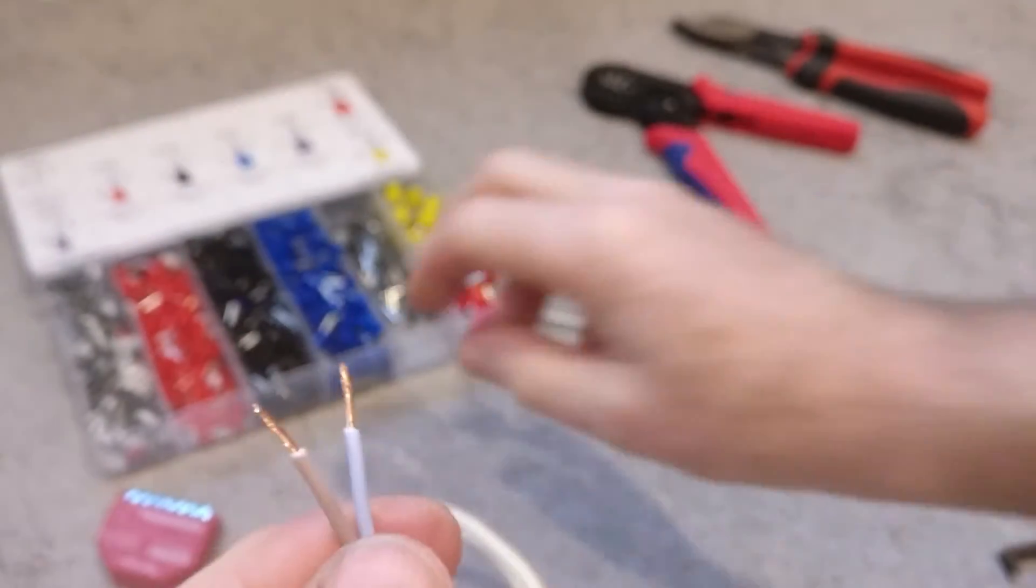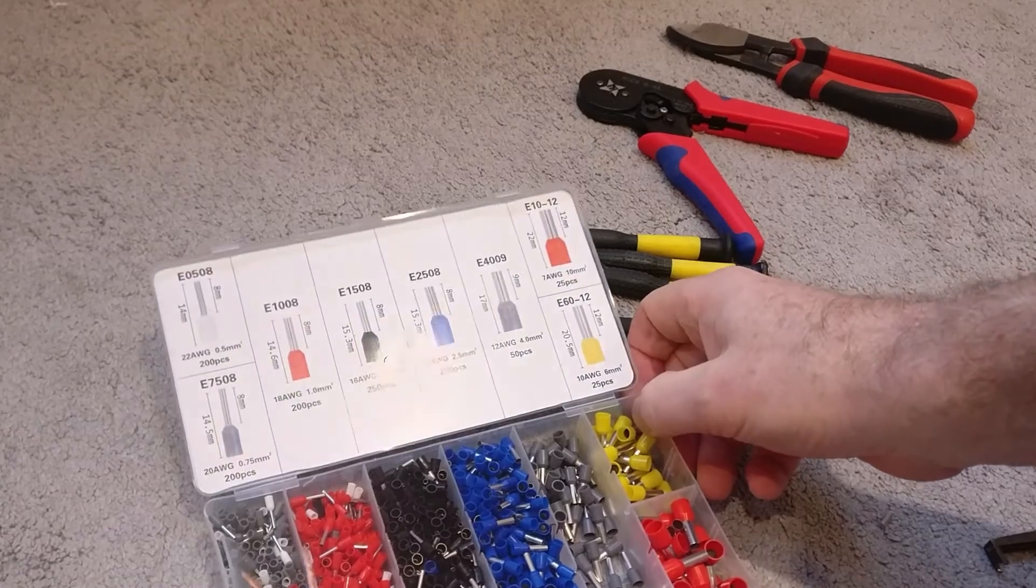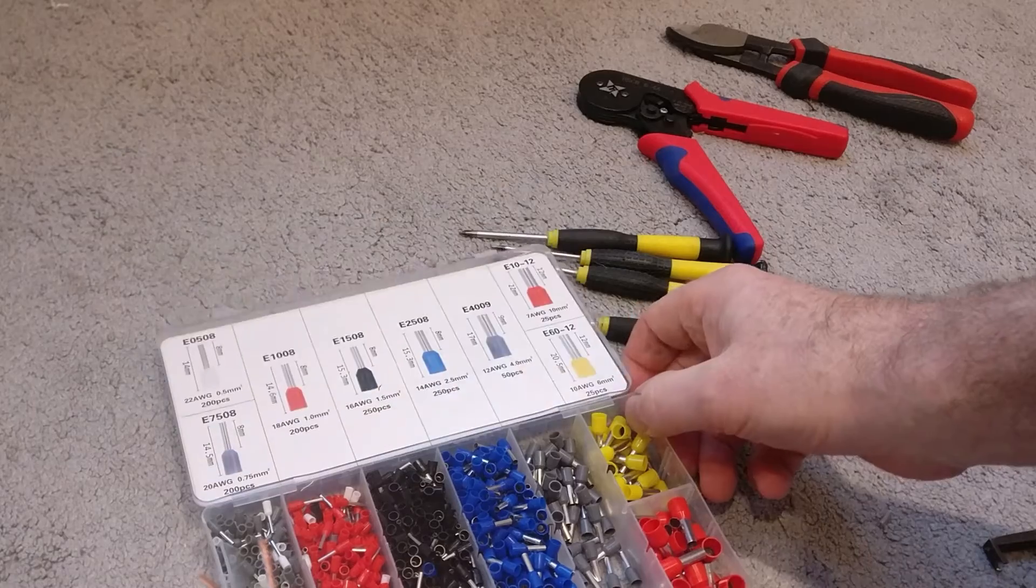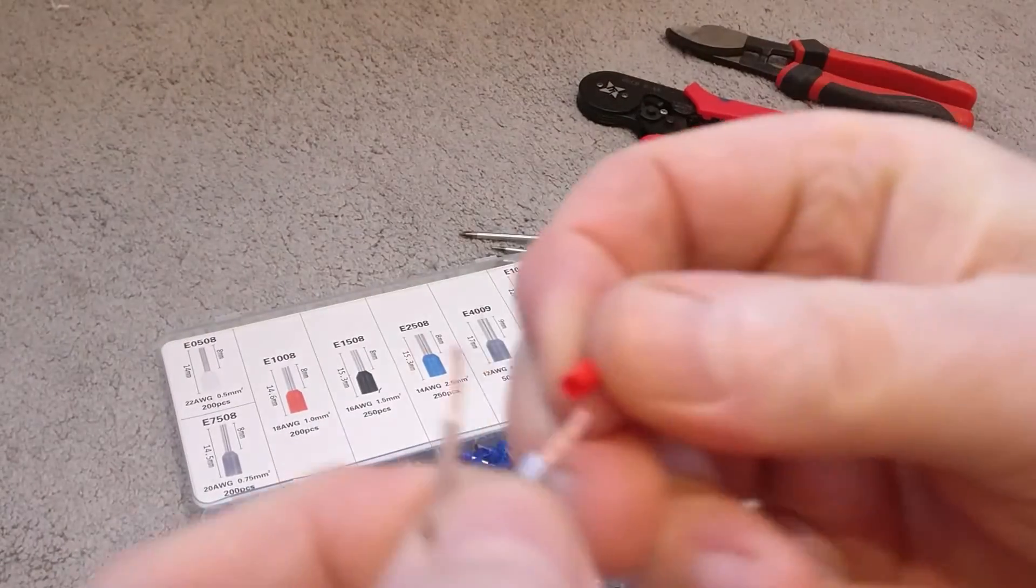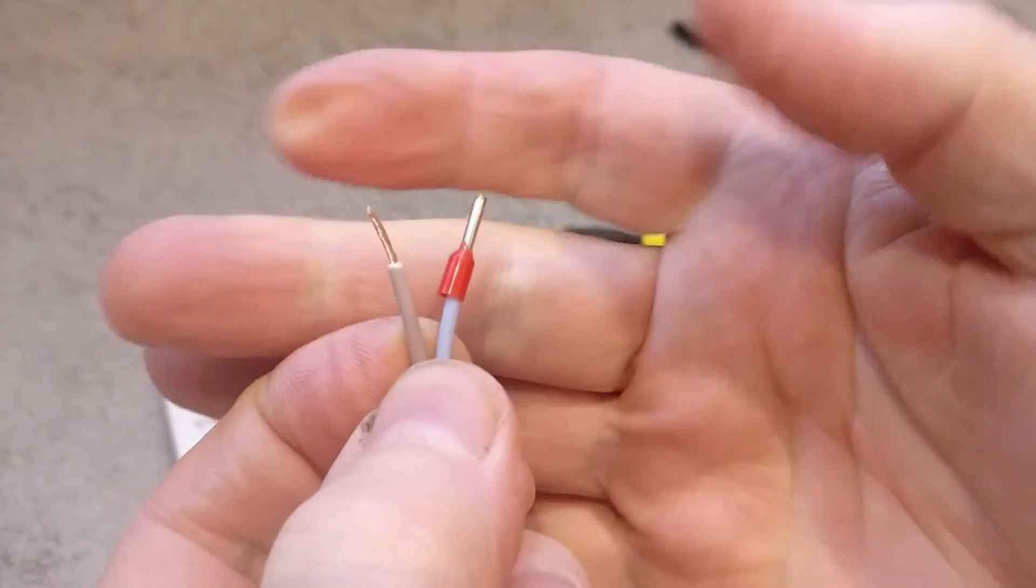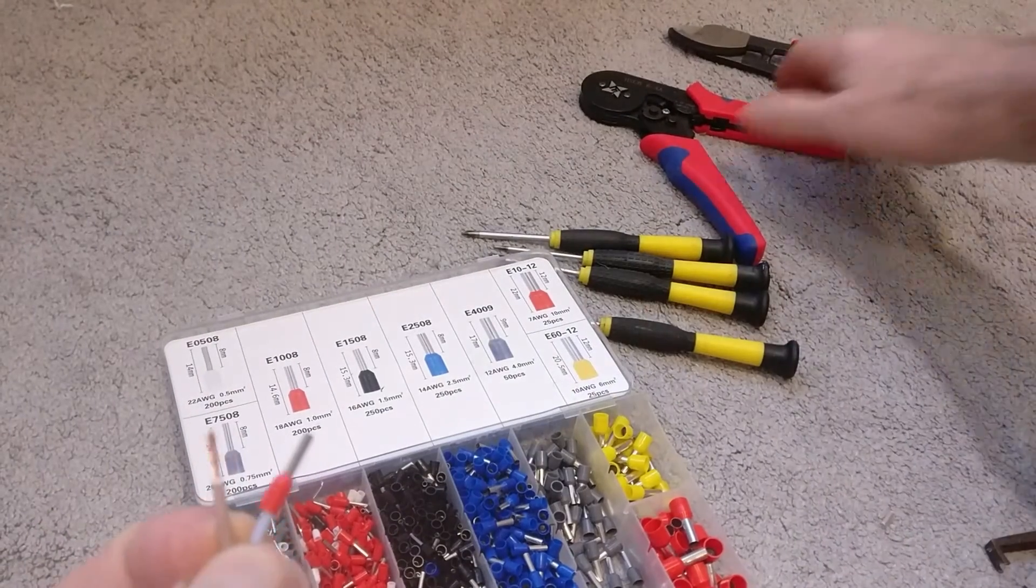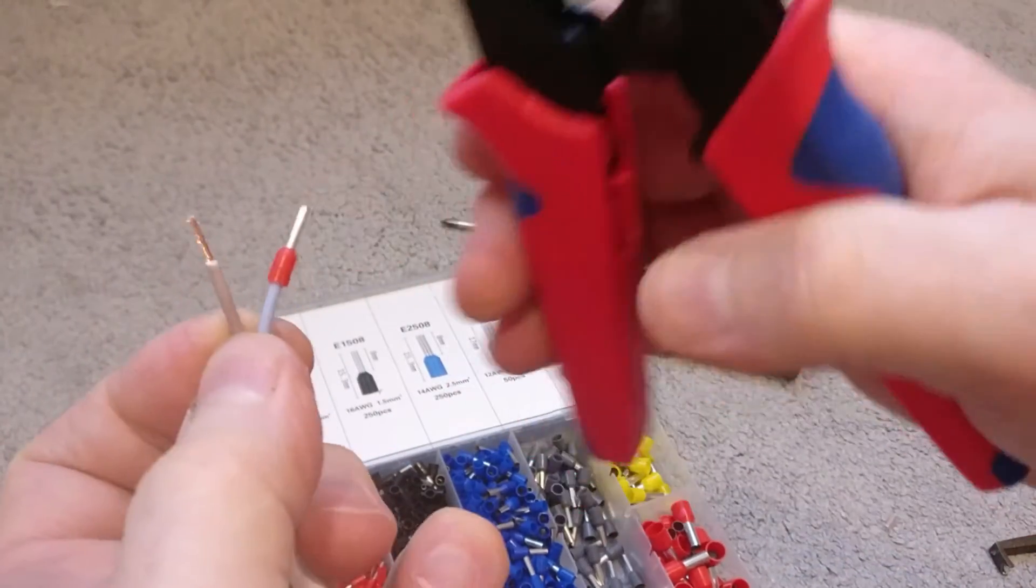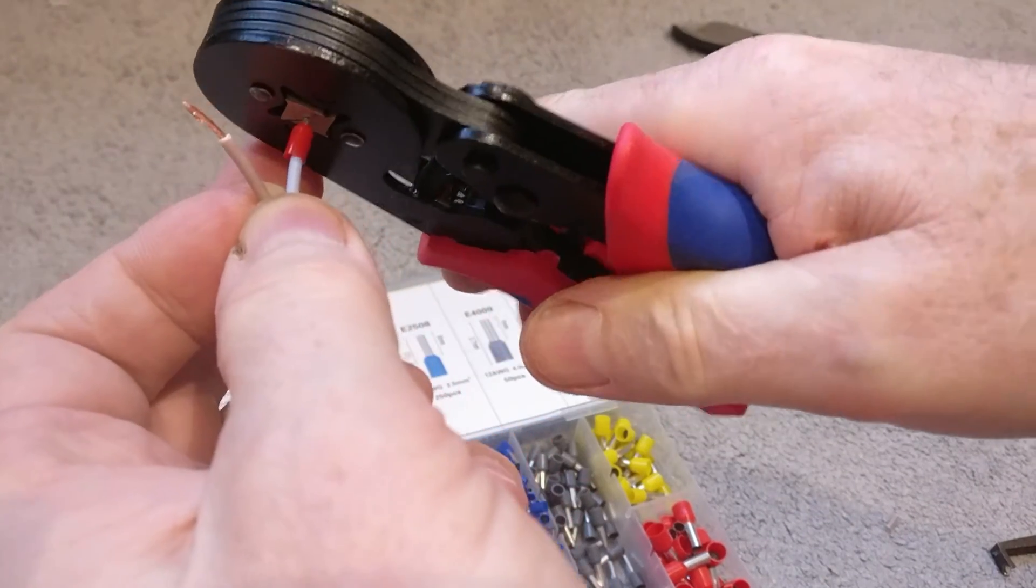As you can see here, twist the cables around just to neaten them up so they go into the ferrule a bit easier. So you can see, just twisting them around. These are 1.5 millimeter squared, so if you just look at the box here, that's going to be this red one I think. Let's just put that in. So all you do is push it on so that the outer core is all the way seated in, and then all you do is get a crimping tool like this. These kits can be bought quite cheaply from eBay or Amazon. Just push it on and then push it in, pull the ratchet.